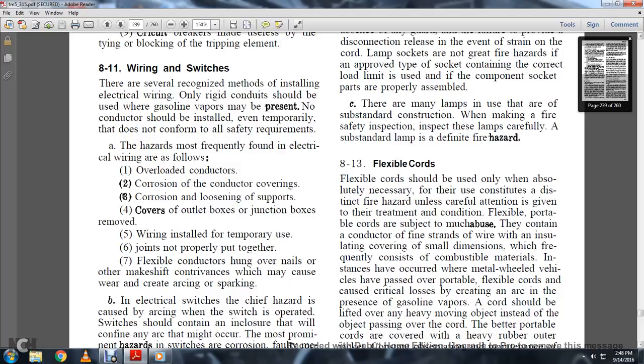8-11. Wiring and switches. Several recognized methods of installing electrical wiring in rigid conduit should be used where gasoline vapors may be present. No conductor should be installed, even temporarily, that does not conform to all safety requirements. The hazards most frequently found in electrical wiring are overloaded conductors, corrosion, worn conductor coverings, loosening of supports, missing covers on outlet boxes or junction boxes, temporary wiring, joints not properly made, flexible conductors hung over nails, and makeshift contrivances.